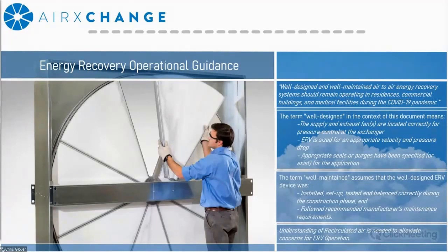Well-designed refers to proper fan location and operating pressure, and that the ERV component has been sized with proper velocity and pressure drop in mind. And the seals have been designed and selected for and adjusted for that application. Well-maintained means that the system was installed, tested, and balanced appropriately, and that the building operators have been following the manufacturer's recommended instructions for any particular maintenance procedures. And in order to minimize potential concern for carryover, I'm going to talk about that in the next couple of slides.